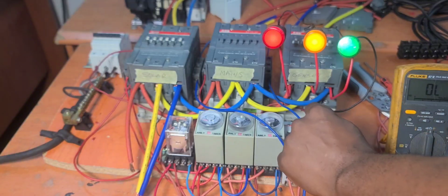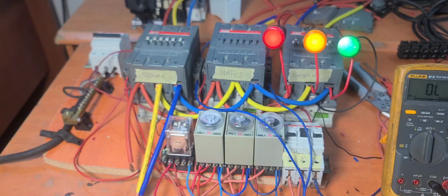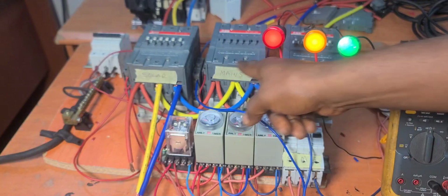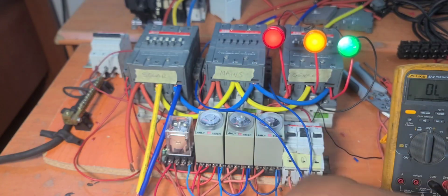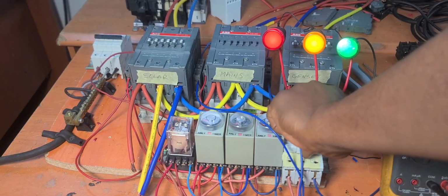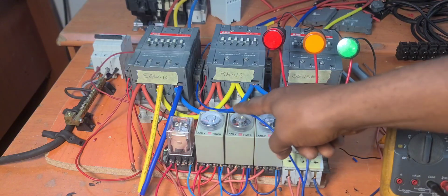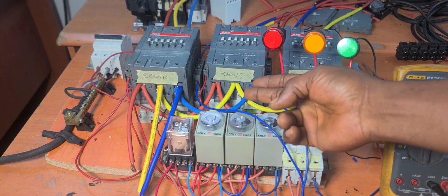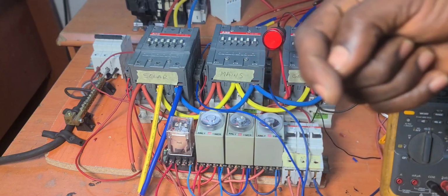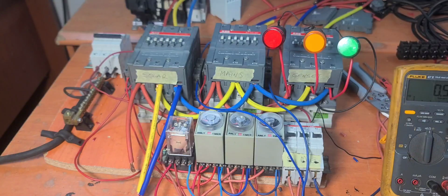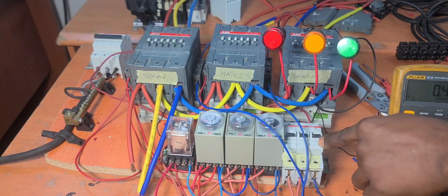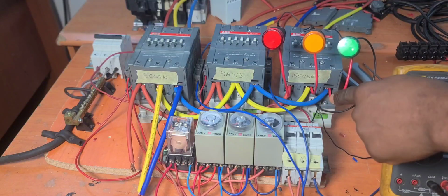Let us switch off this generator. It isn't supposed to be on at this time. All right, let us just switch it off, because the signal that's supposed to start it is going to come from these two wires. So if mains fails by switching off this one, now you are going to hear that beep, meaning that this wire has been short at that side. And that short here sends a signal to the controller on the generator to start the generator set. So when the generator set starts, power is going to come here. Remember, there's not going to be power here until generator set starts.